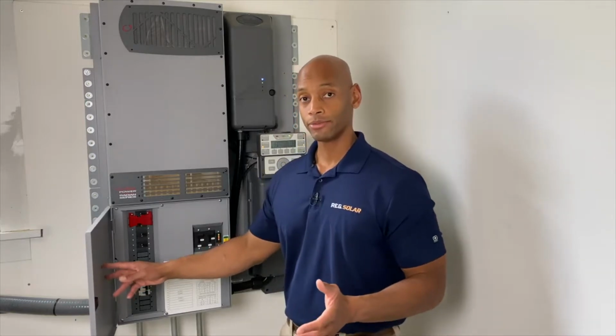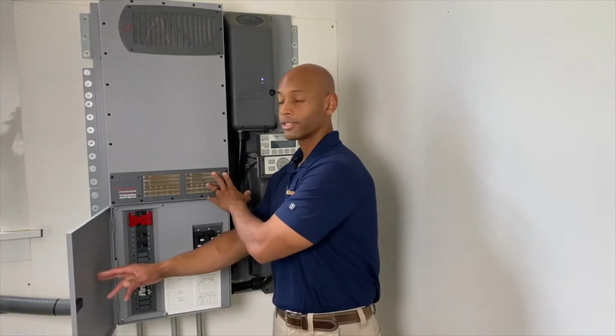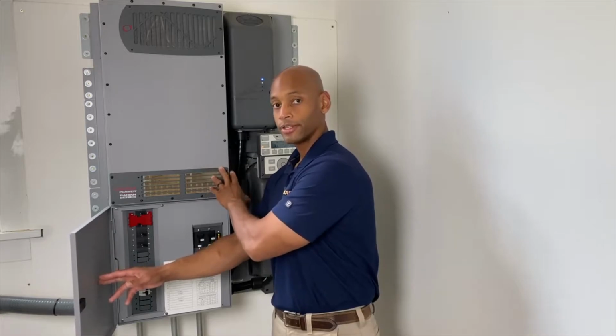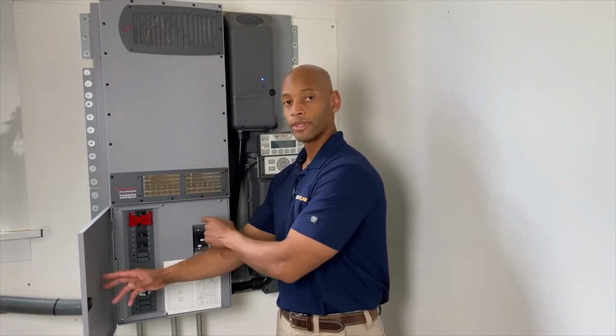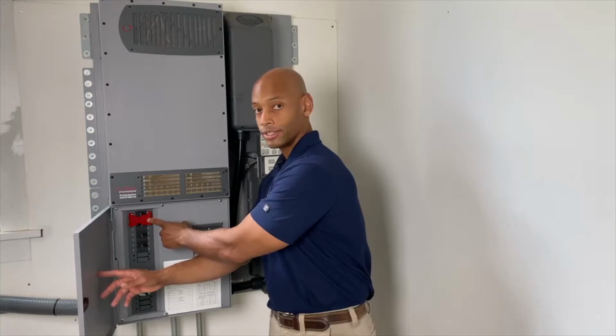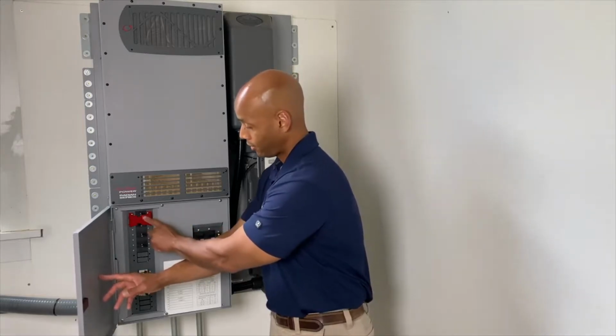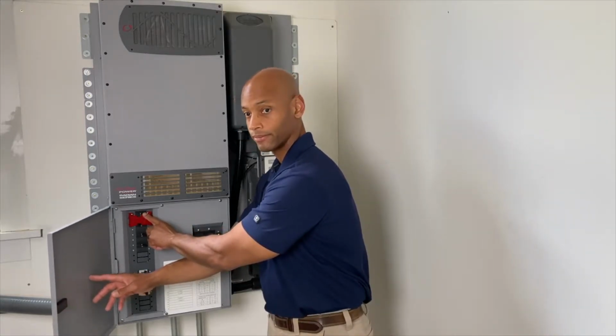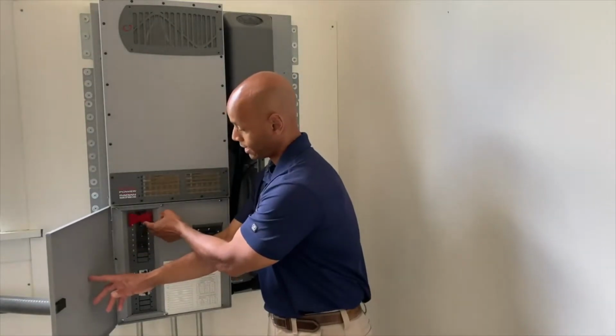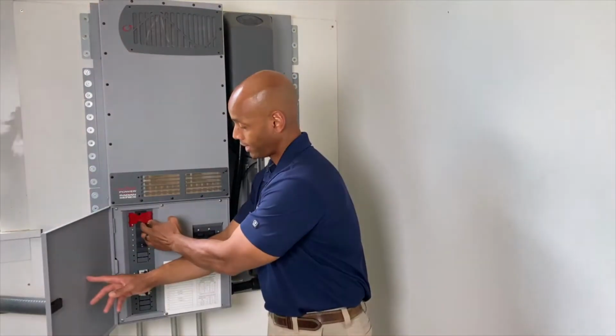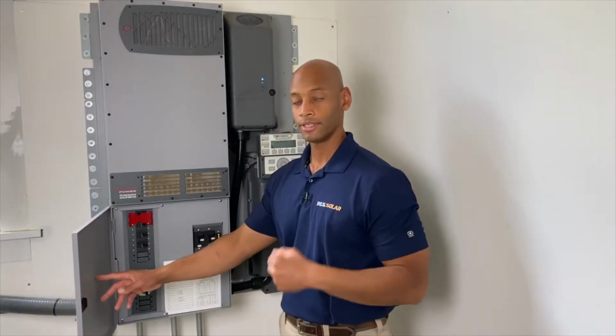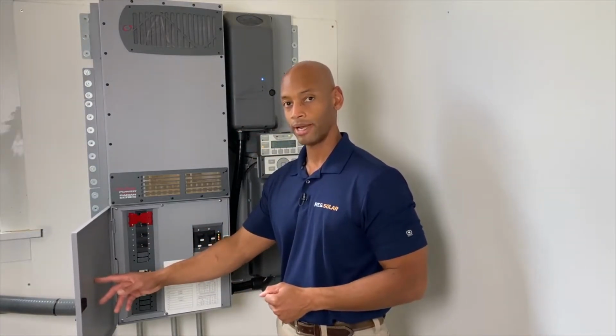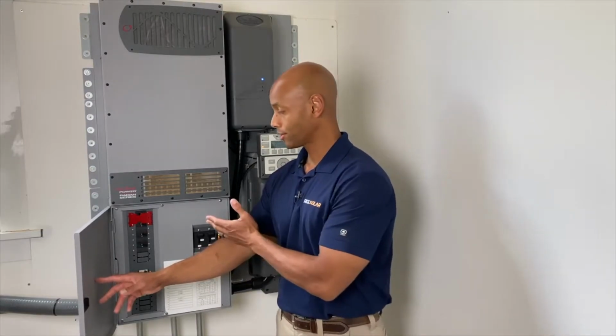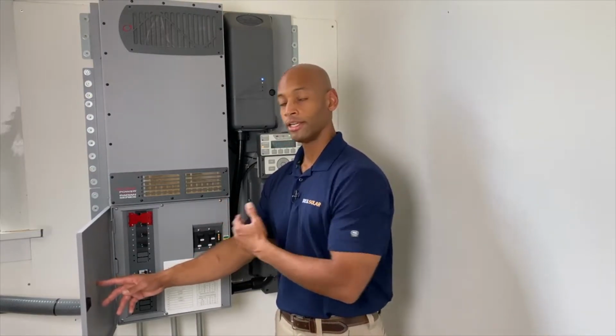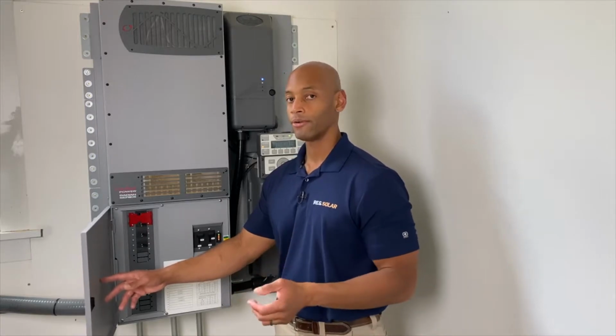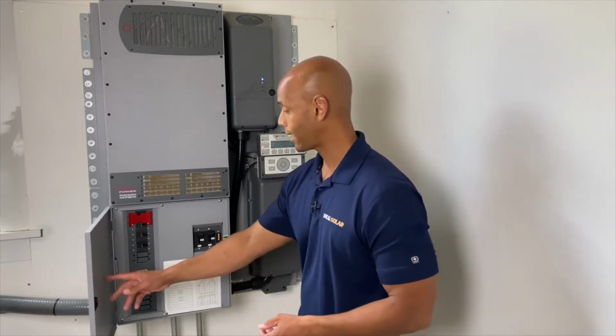The grid bypass switch is important because if the inverter ever were to have a fault, or it needs to be serviced or work done on the unit, you can always fail back over to utility power by turning off the AC output, sliding up the interlock, and turning on the bypass switch. So now we're running back on utility power here. Under normal circumstances, you shouldn't have to use this at all. It's really only if the unit malfunctions or has to be serviced. So we'll go ahead and switch that back now.